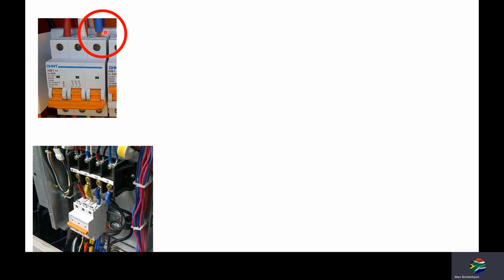Here you can see bad work practice. This is on a VRV system. They decided to put a breaker in the unit, and they screwed a metal plate over here. So with a metal plate, the breaker technically can't break. It can't trip in the event of a fault. So remember, the breaker is there to protect the cable from burning and catching alight. And here it's not going to be able to trip because there would be a metal cover over this, preventing it from tripping.